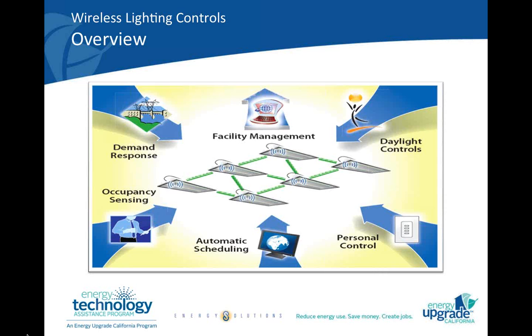Additionally, you see components under the personal controls, daylight controls, occupancy sensing. All of these controls also are equipped with a wireless sensor. So you can have a wall control that isn't necessarily wired to any fixtures at all. All it has is a wireless sensor in it. Same thing with an occupancy sensor or a photocell. And now these controls become part of that network. Once you have this network set up, this information is then channeled through a gateway, which then feeds into the building network and is accessible through an interface that's either online or on your desktop computer or even your iPhone.